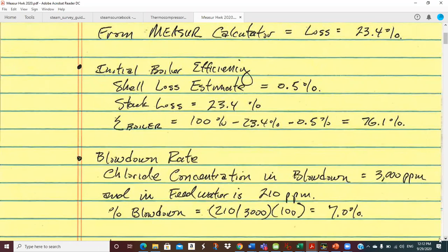I put a half percent for shell loss, just an estimate. If I was out there doing this and I wanted to take my infrared camera, take measurements, calculate the area of that boiler, and try to calculate what I actually think the heat transfer loss rate is, I can certainly do that. Is that justified? Maybe, probably not, unless there's something strange going on — you see something that you think is just really not right. But at any rate, you probably should have some accommodation for shell loss.